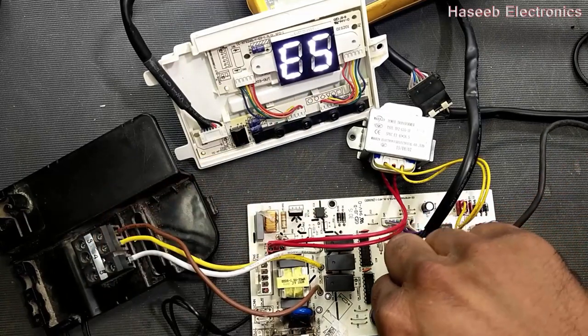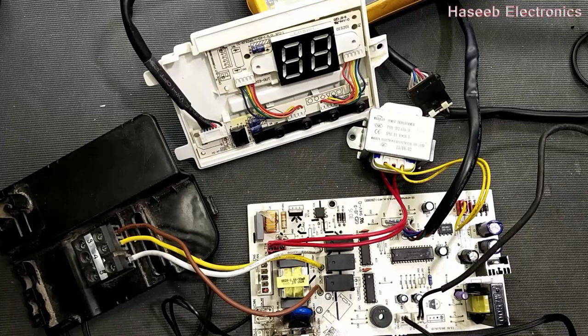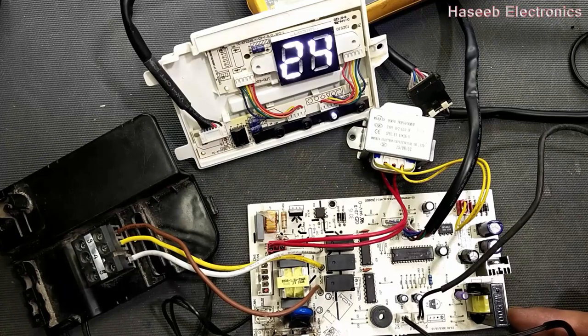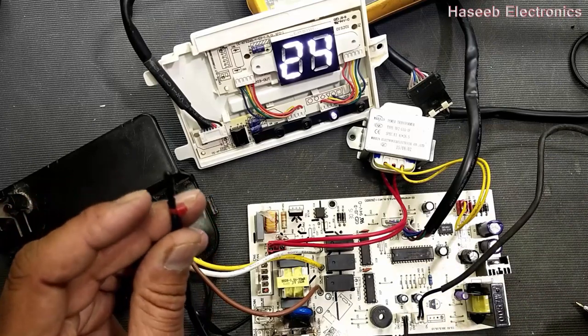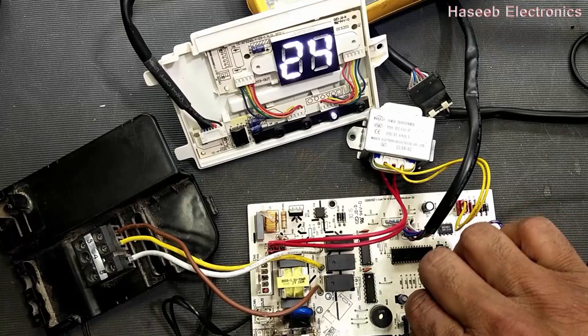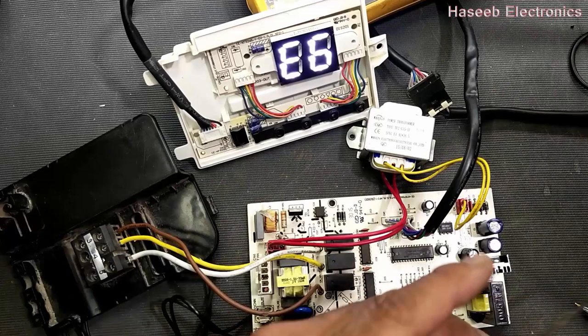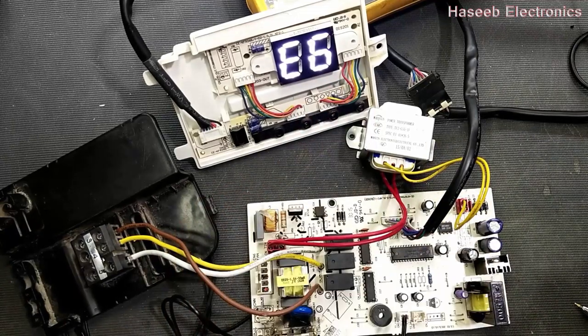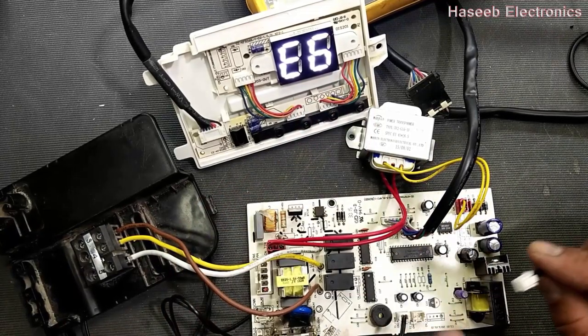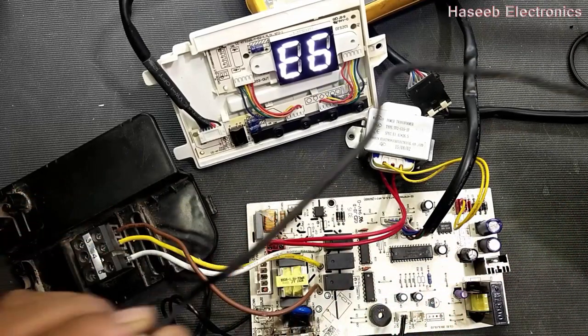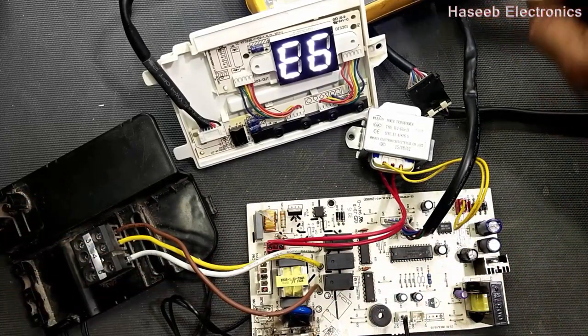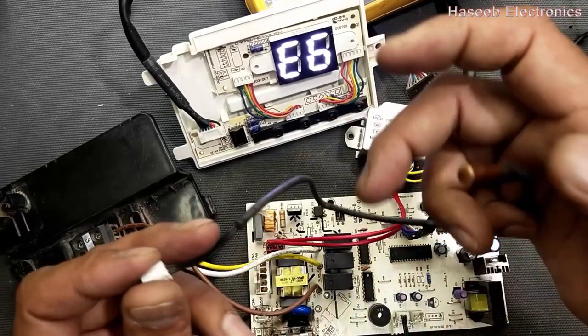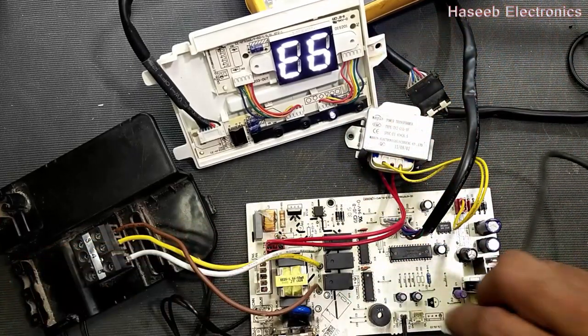Now I am going to connect the sensor. It will reset. Make reset, it is on. This is the room temperature sensor error, E5. If E6, I remove this pipe temperature sensor, it will generate an E6 error. At that time, you have to check the connector, cable and sensor, as I mentioned in the test procedure for this connector. So you have to test this, and now I am going to connect this sensor.